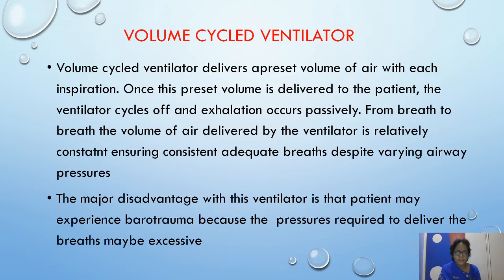Next, what are the volume cycle ventilators? A volume cycle ventilator delivers a preset volume of air with each inspiration. See, we will set the ventilator so that a constant volume of air will be delivered to the lungs by inspiration. Once this preset volume is delivered to the patient, the ventilator cycles off and exhalation occurs passively.